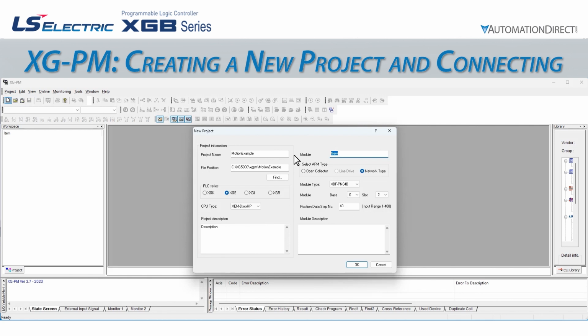We can give our project a description for future programmers to reference, and we can name our module. We will call our module Pulse Train Module. This CPU has the option to use the onboard Open Collector Pulse Train outputs or an EtherCAT network motion application. We will be using the onboard Pulse Train, so we will ensure the APM type is set to Open Collector. For our module type, we only have the option to use XBF-P006E. This is because we are using the onboard Open Collector outputs with the HP CPU type.